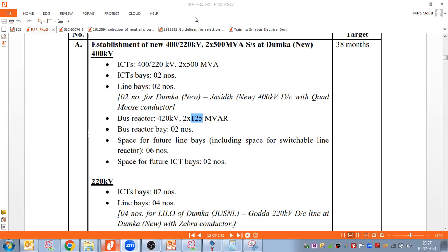Sir, I am getting that, but do we have an AVR kind of system to regulate this? No, there is a power factor controller which senses the requirement of power factor for MVAR, and which switches on the capacitor bank as per requirement, or reactors as per requirement. So this is done automatically? Yes, there is a controller that will detect and switch on the reactor.